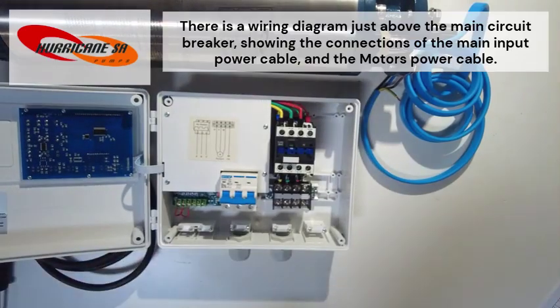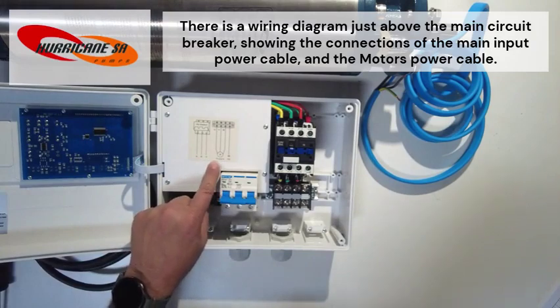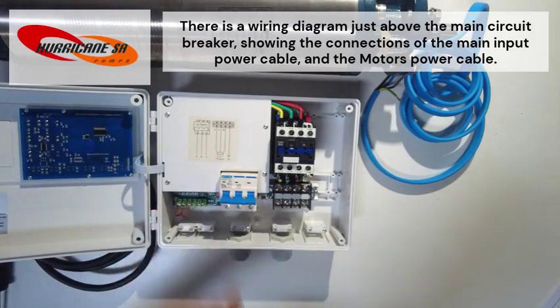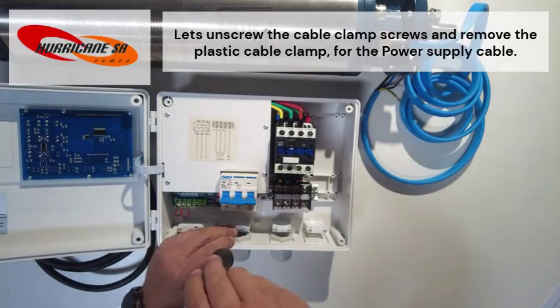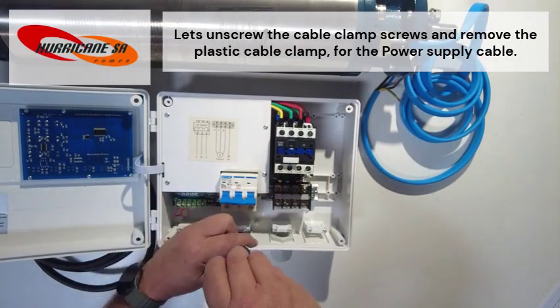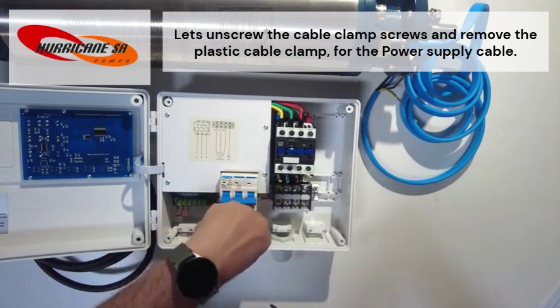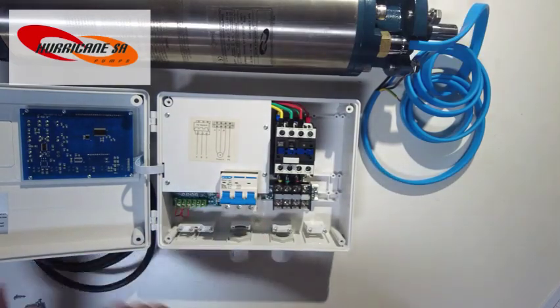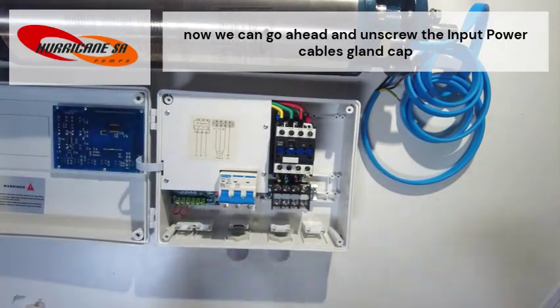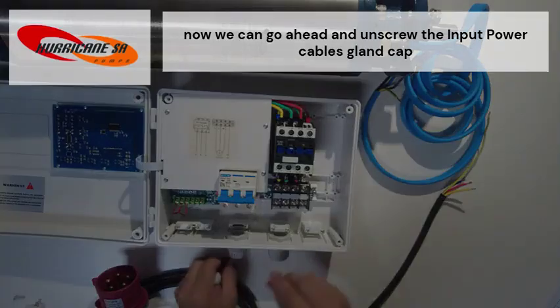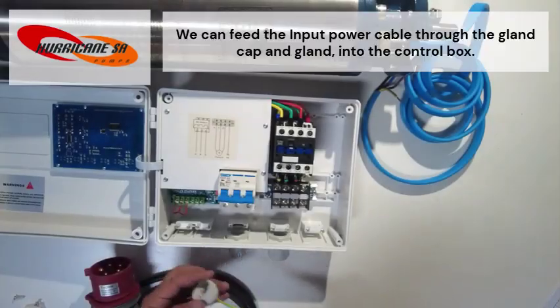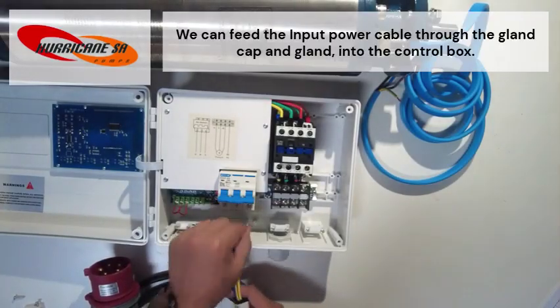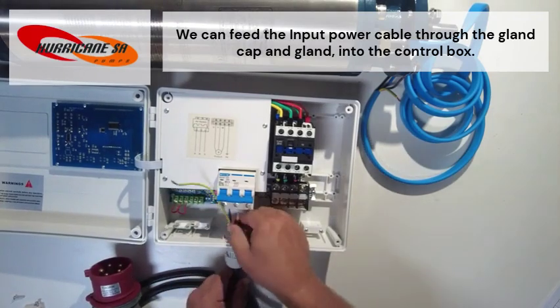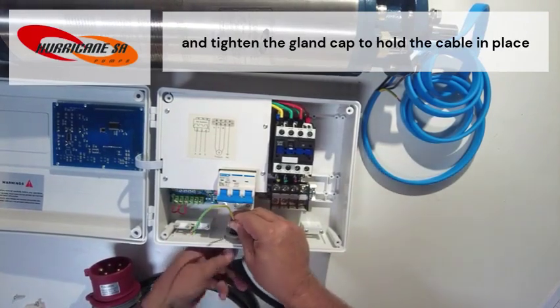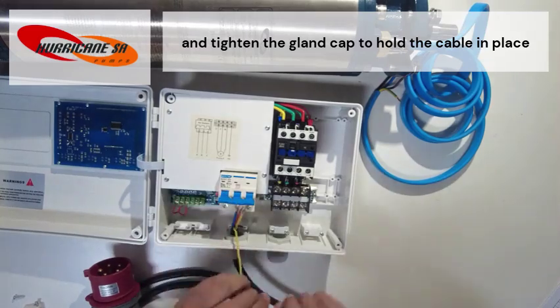There's a wiring diagram just above the main circuit breaker, showing the connections of the main input power cable and the motor's power cable. Let's unscrew the cable clamp screws and remove the plastic cable clamp for the power supply cable. Now we can go ahead and unscrew the input power cable's gland cap. We can feed the input power cable through the gland cap and gland into the control box, and tighten the gland cap to hold the cable in place.